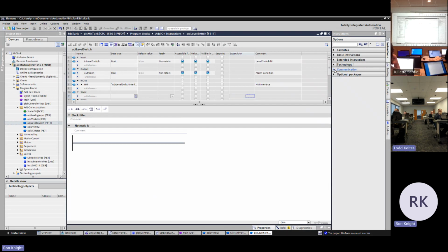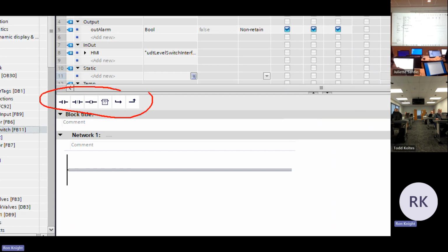And then finally, communication, if you're doing PLC to PLC communications, Modbus TCP, Modbus RTU, think message instruction, to use Rockwell terms. You can even get a Siemens PLC to talk to a Rockwell PLC. There's not a built-in, but there's a free function block you can download from the Siemens website if you need to do that. But pretty much everything we need is right here.